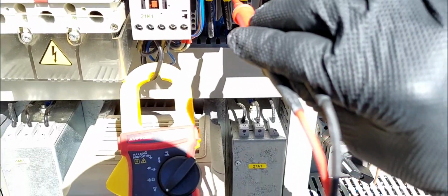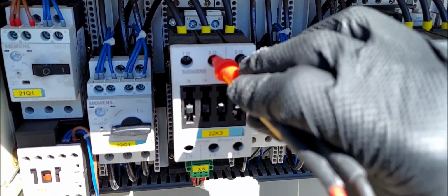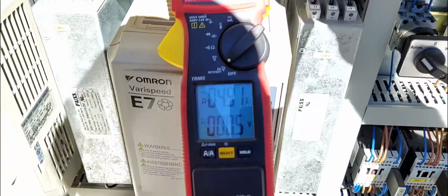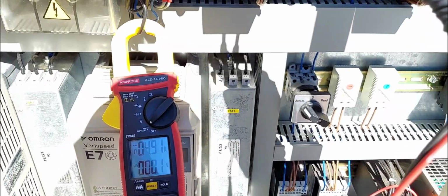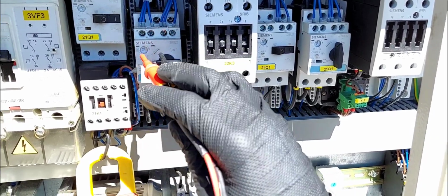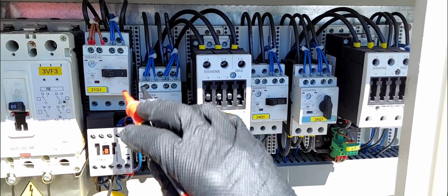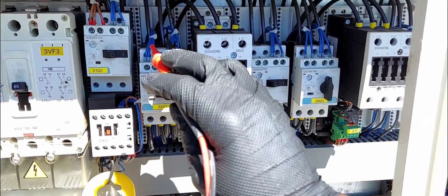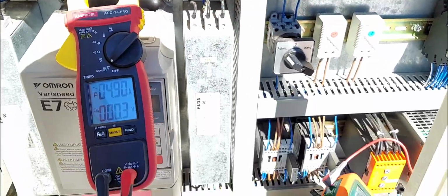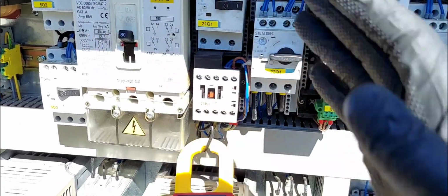If I go to the bottom, right there, it's dead. If I go to my contactor, okay, it's dead. So I can work from here, where the power is supposed to come in. It leaves the overload, or down here in the bottom, comes around. So from here is dead, up here is hot. All right, dead, dead, dead, hot. So I can work. Again, the best practice is always to shut down the main power while you're working, but I've already explained why I can't do that right now.